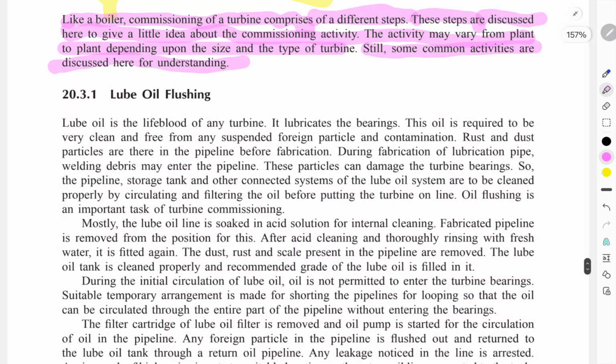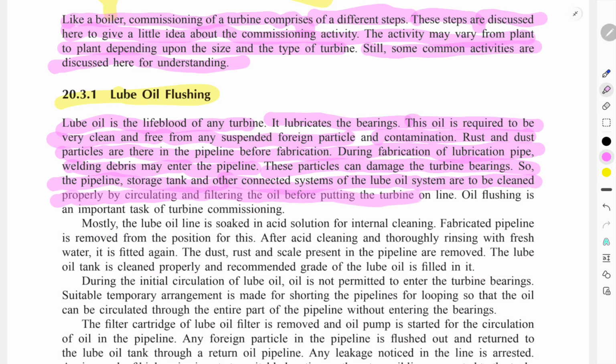Lube oil flushing. Lube oil is the lifeblood of any turbine. For lubrication of the bearing, the oil is required to be very clean, free of suspended foreign particles. Contaminated rust and dust particles are there in the pipeline from fabrication. During fabrication of the lubrication pipe, welding debris may enter the pipe. These particles can damage the turbine bearing, so the pipeline, storage tanks, and other connecting lube system are to be cleaned, and the oil properly circulated before putting the turbine on line. The flushing is an important task of the turbine commissioning.